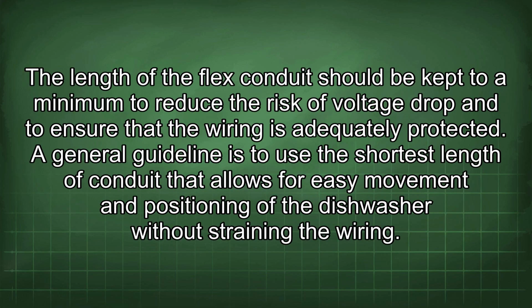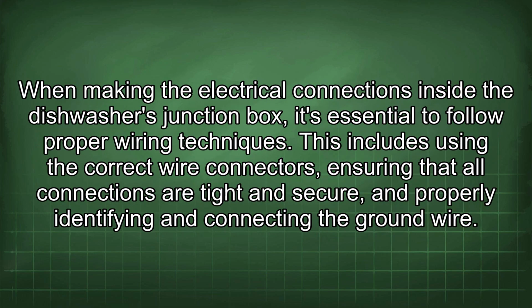The length of the flex conduit should be kept to a minimum to reduce the risk of voltage drop and to ensure that the wiring is adequately protected. A general guideline is to use the shortest length of conduit that allows for easy movement and positioning of the dishwasher without straining the wiring. When making the electrical connections inside the dishwasher's junction box, it's essential to follow proper wiring techniques.